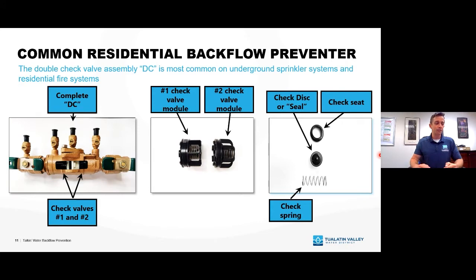Since there are two check valves, that means there are actually two independent barriers between the drinking water and a non-potable substance. Because these assemblies contain springs, rubber seals, O-rings, and seats, like anything mechanical, these components can wear out, break, or malfunction, which is why the annual test is so important. For this assembly, both check valves would have to fail simultaneously for contamination actually to occur. So just a quick breakdown. On the left-hand side, here's just a complete unit, including shutoff valves and test cocks for the testing purposes.